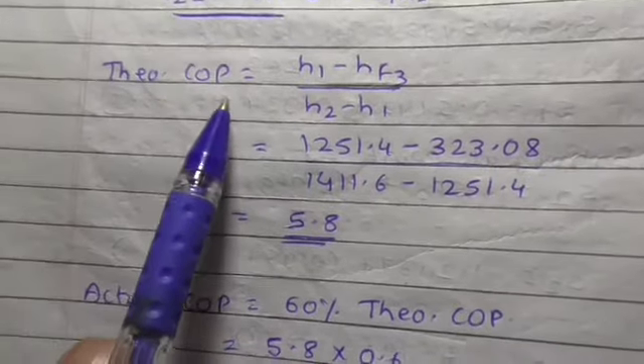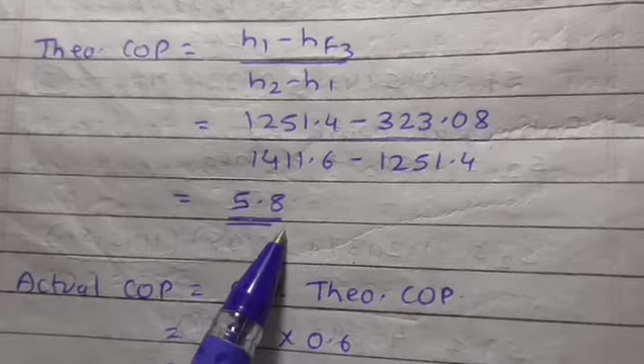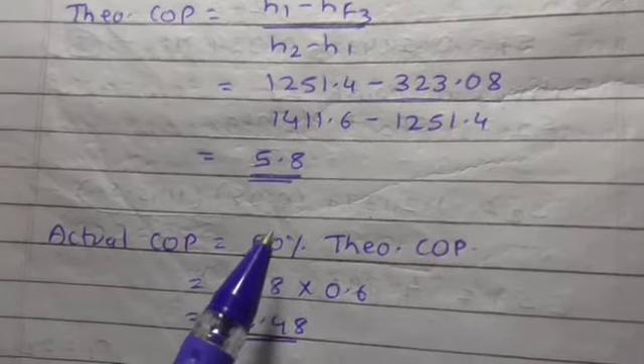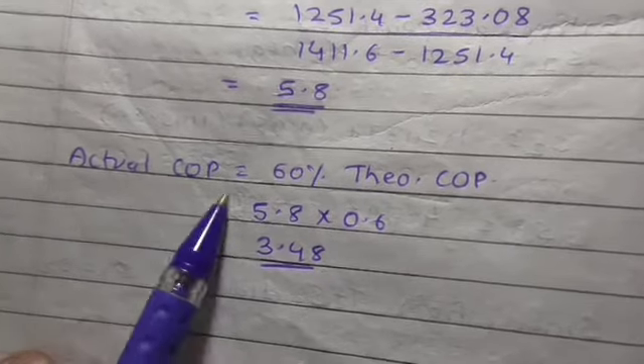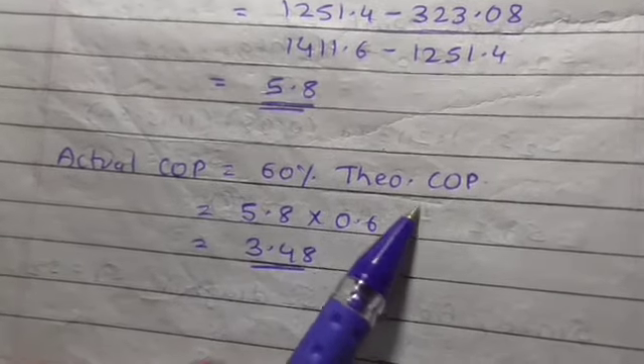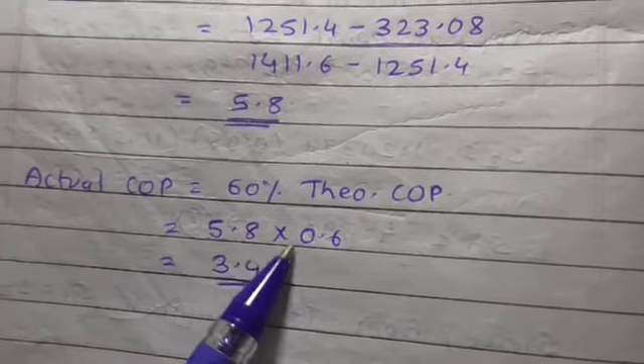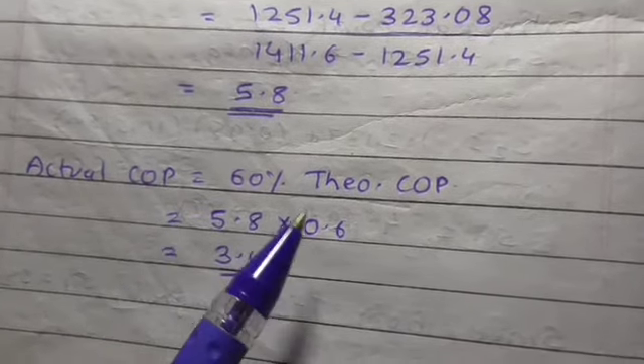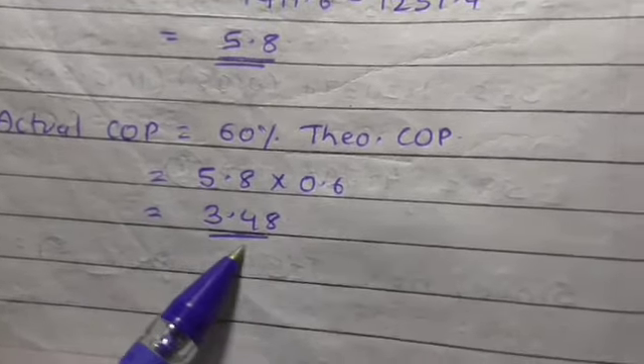Then theoretical COP: H1 minus HF3 divided by H2 minus H1. This is the same procedure we have adopted for all the problems. Theoretical COP is 5.8. Actual COP was to be calculated as 60% of theoretical COP, so 5.8 times 0.6, we get actual COP as 3.48.